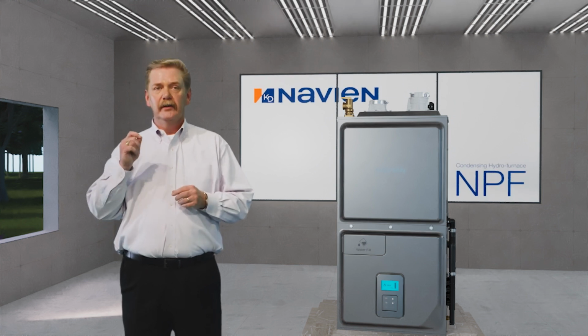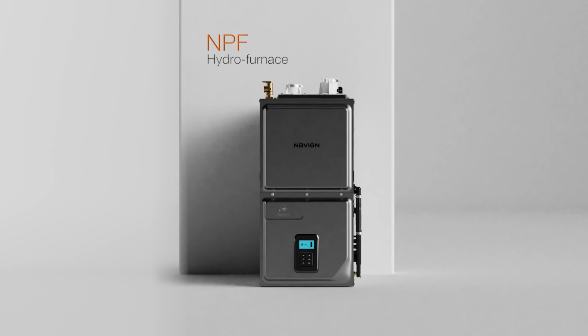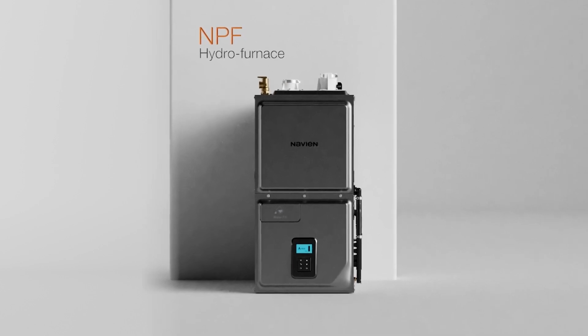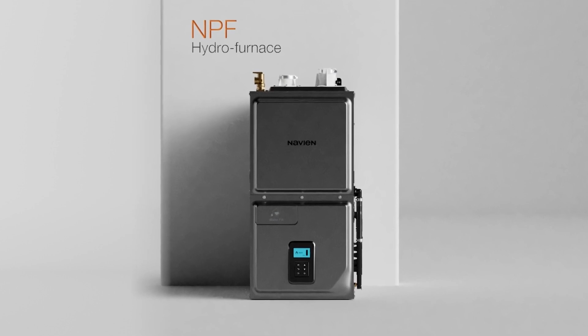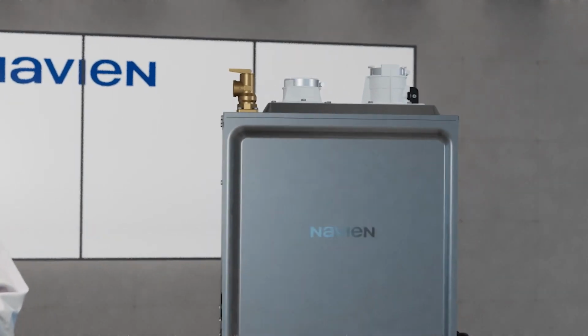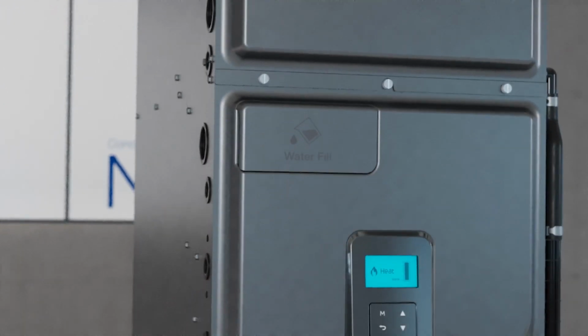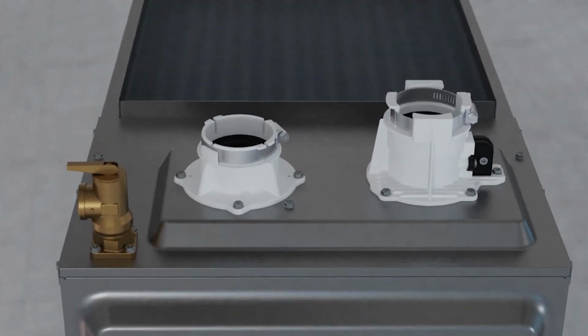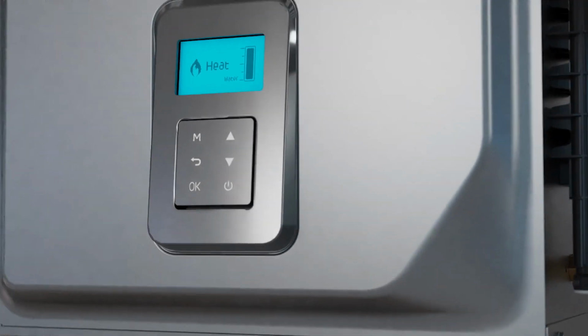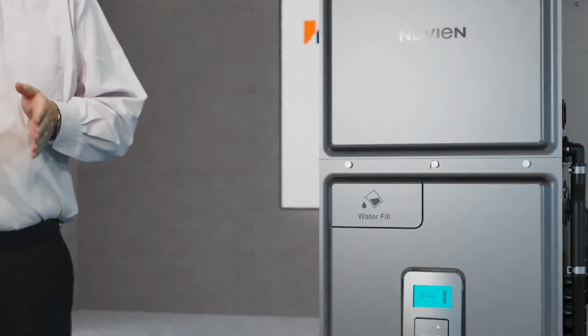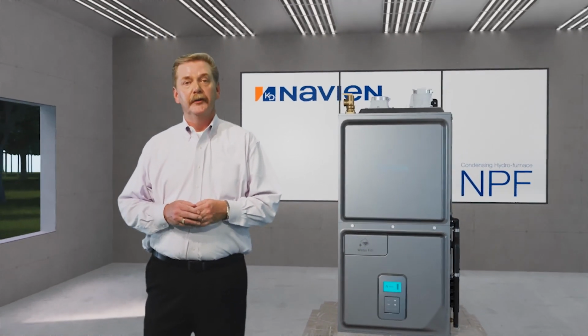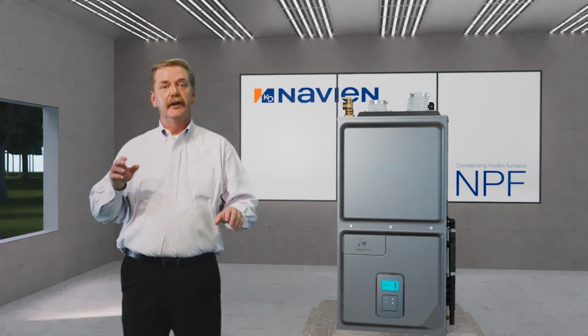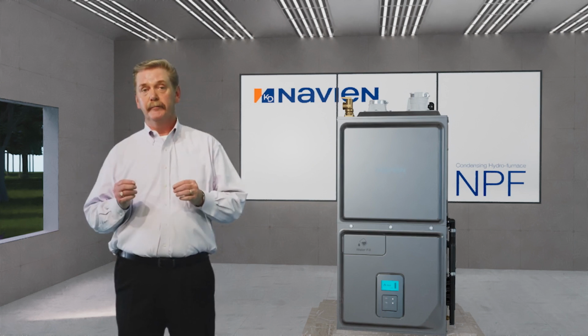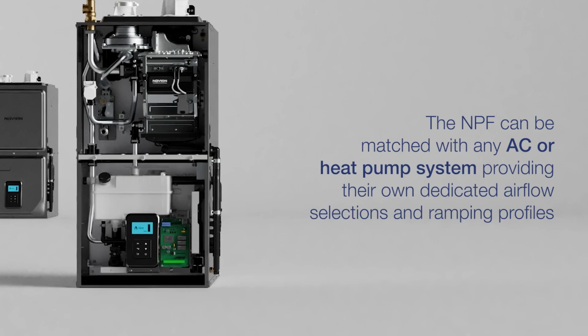Now, I think it's important that we dive a little further into how these systems leverage technologies that many of you are already familiar with and that have made Navien products trusted for years. The NPF draws from Navien's rich history of leveraging water to create superior home comfort solutions, using heated water in conjunction with an ECM variable speed blower to provide selectable airflow and discharge air temperatures to meet the specific conditioned space requirements. Now, the system automatically balances airflow, discharge air temperature, and heat capacity to provide comfortable, even temperatures throughout the home. The NPF can be matched with any AC or heat pump system providing their own dedicated airflow and ramping profiles.